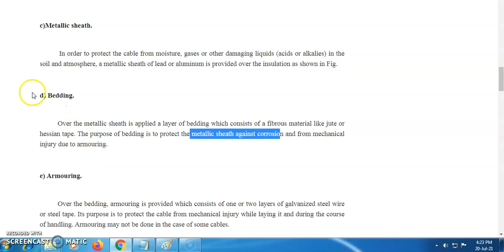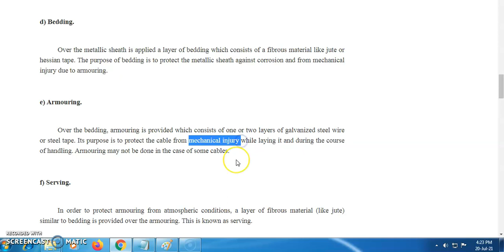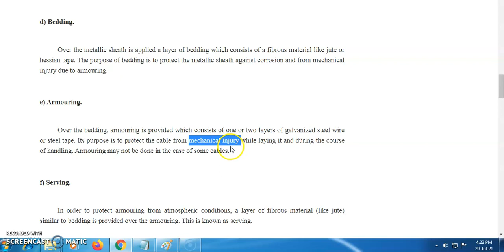Over the bedding, armoring is provided which consists of one or two layers of galvanized steel wire. You have seen a wire wound around like a tape. Galvanized steel wire or steel tape. Its purpose is to protect the cable from mechanical injury. So already there is a small layer of jute, and over that there is a metallic layer to provide mechanical safety. Armoring may not be done in the case of some cables. This mechanical armoring will be there only in high voltage rating cables.